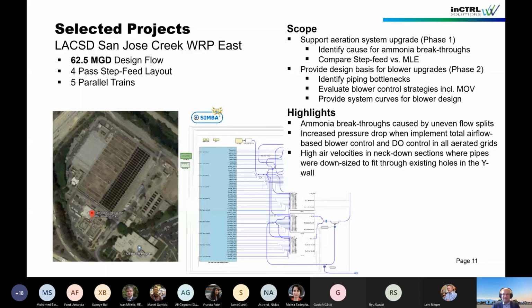Some of the highlights: we found that the ammonia breakthroughs were caused more by uneven flow splits as opposed to any inhibition of nitrification. One thing we found when looking at the aeration system was that when we went to a blower control strategy with total airflow-based blower control, and DO control in all the aerated grids, which they didn't currently have but wanted to look at, the overall pressure drop increased, and they had to go to a blower with a higher discharge pressure than the blowers they currently had. So that was quite an important thing that came out of the work.